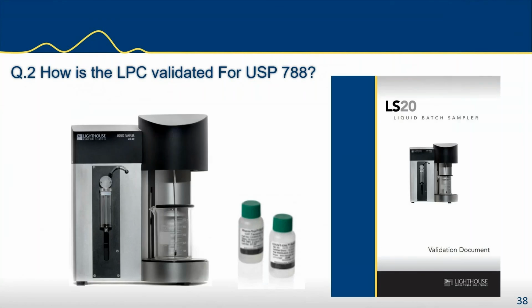How is the LPC validated for USP 788? Again, I did say that's a topic for a whole webinar by itself, but let's just go through some of the requirements. So USP 788 validation and calibration intervals are on a 6-month basis, or even if you move the sampler, you need to revalidate. The basic validation requirements include the verification, which is acknowledged when the liquid particle counter passes the count ratio testing using 15 micron particles, and the corresponding counts should fall within 10%.